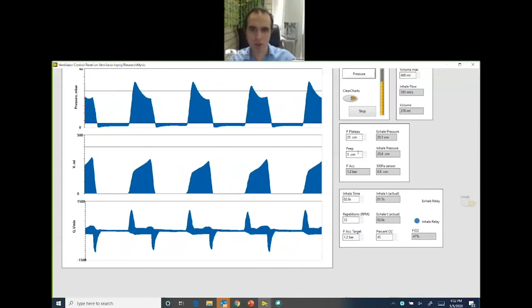So I will hide this to show you what it is made of. So this is a ball valve that we control with the servo motor. If we want to allow more air to go into the lungs at different rates, we have a special type of control algorithm that we use in instrumentation and control. We have a PID controller attached to this servo motor, so that we will be able to control the flow of air into the lungs of the patient. And after the patient inhales the mixture that we got from the oxygen and from the conventional air, he will have to exhale. So we also control the exhale process by this solenoid.